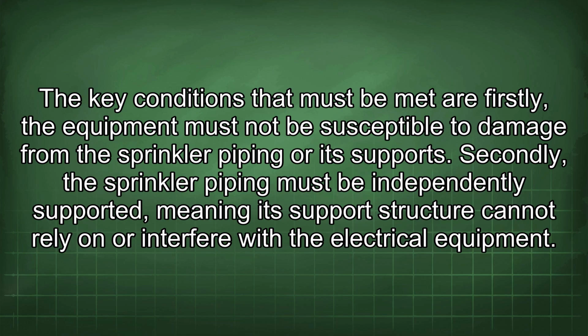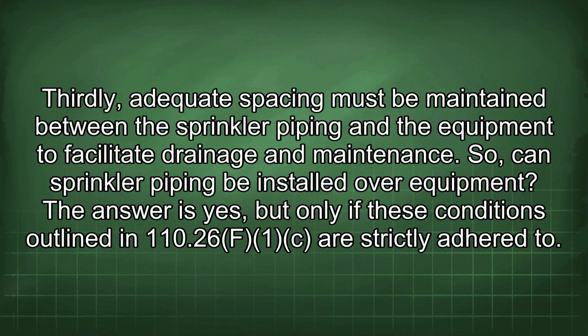The key conditions that must be met are: firstly, the equipment must not be susceptible to damage from the sprinkler piping or its supports. Secondly, the sprinkler piping must be independently supported, meaning its support structure cannot rely on or interfere with the electrical equipment. Thirdly, adequate spacing must be maintained between the sprinkler piping and the equipment to facilitate drainage and maintenance. So, can sprinkler piping be installed over equipment? The answer is yes, but only if these conditions outlined in 110.26(F)(1)(c) are strictly adhered to.